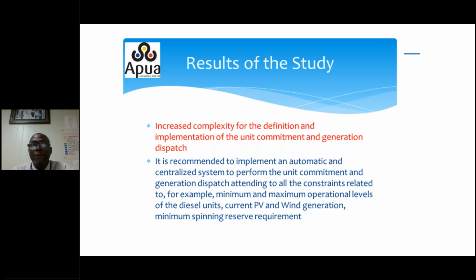Now, we know that we purchase power from the IPP. What happens sometimes is that we have an energy contract per se. So towards the end of the year, we have to meet a minimum guaranteed amount of energy. So at times, you're forced to put all the sets on at a particular plant. Now, that might not necessarily be the schedule that you would want to meet the technical concerns, but you might have to do that to meet financial concerns. So you always have to weigh the technical issues versus the financial issues.